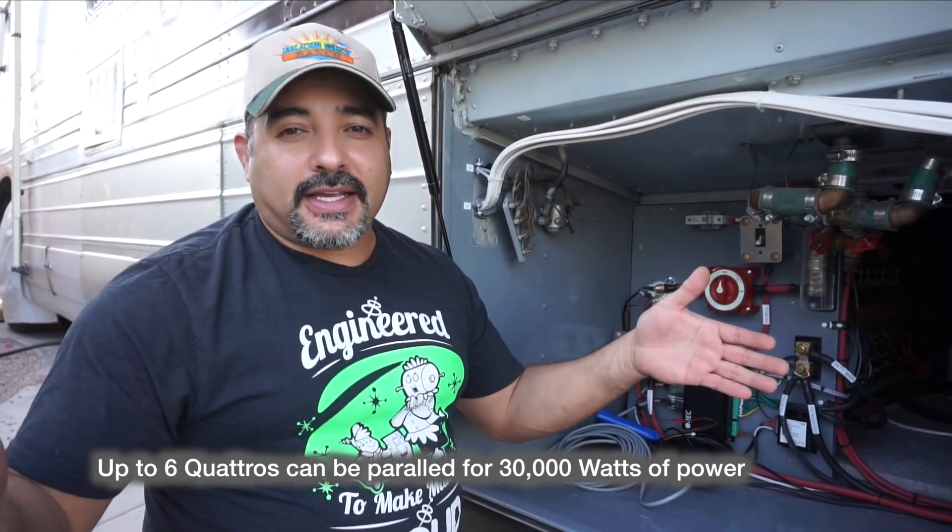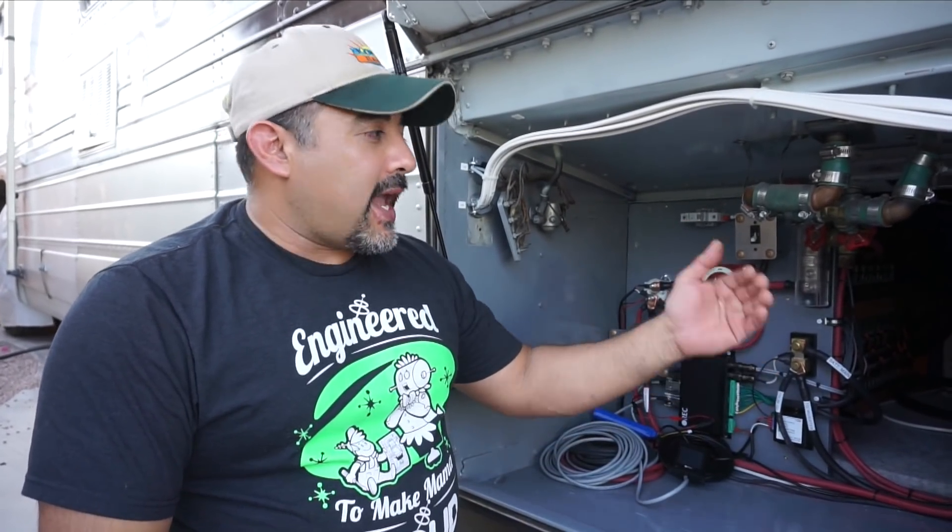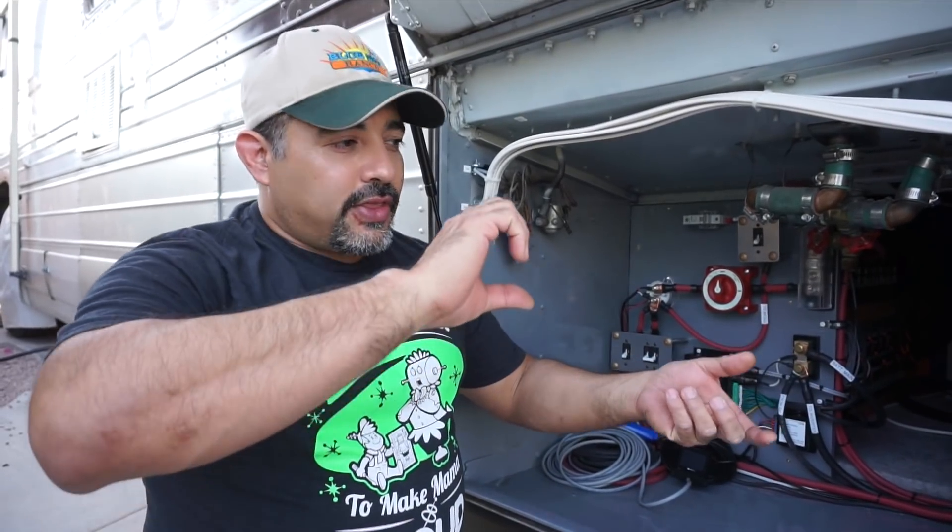Another reason we chose this particular inverter is that you can parallel configure them. If 5,000 watts wasn't enough and we needed 10,000 watts, we could run two of them and they'd talk together to produce 10,000 watts, all the way up to six units. We could also buy another one and configure them to provide 240 volts — so instead of 5,000 watts at 120 volts, we'd get 10,000 watts at 240 volts, essentially doubling the wattage.